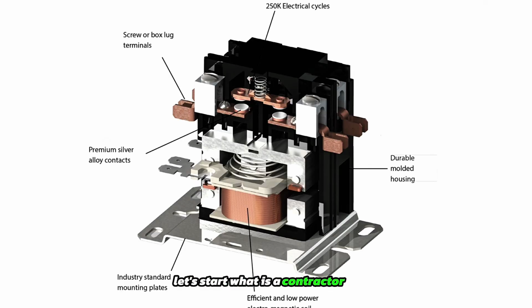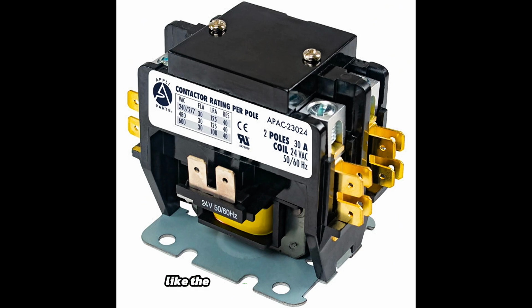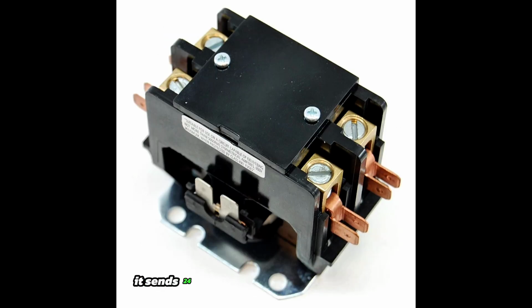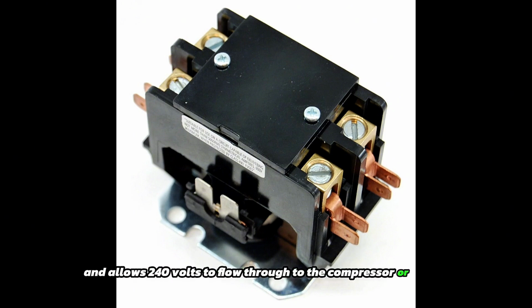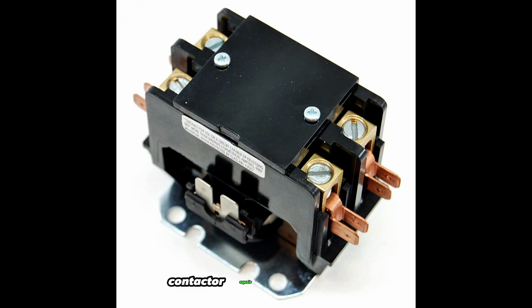What is a contactor? A contactor is a heavy-duty switch. It controls the high voltage going to components like the compressor or fan motor. When the thermostat calls for cooling, it sends 24 volts to the coil of the contactor. This pulls the internal contacts closed and allows 240 volts to flow through to the compressor or fan motor. Contactor equals low voltage in, high voltage out.